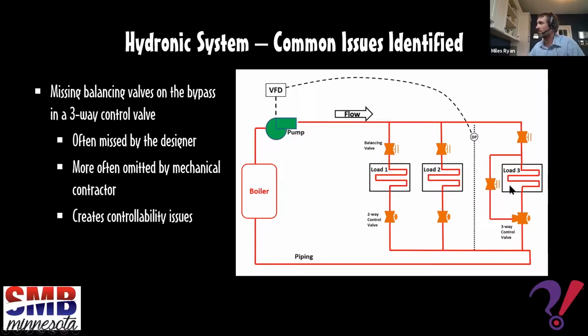So what had happened was this particular coil, this is a heating coil on an air handling unit. It was spring. It didn't have much heating requirements. It was actually on a dual duct system, in the hot deck on a dual duct system. So it had some heating requirements, but not much. Therefore, this port was closing a bit. This port was opening, but as soon as you open the port to the bypass, if you don't have a balancing valve there, that's a short circuit. So now all the water was short circuiting around that coil. The differential pressure was dropping when you'd expect it to increase when you're having a loss in heating requirements.